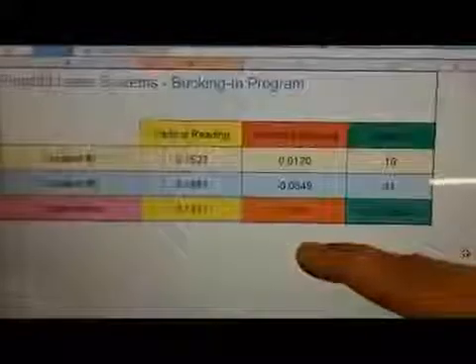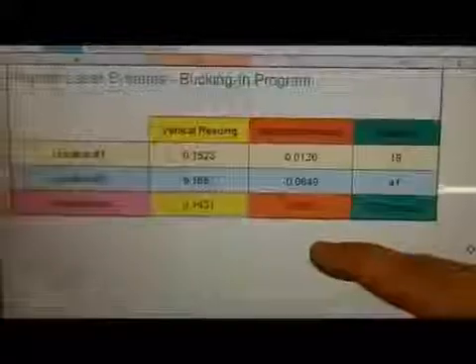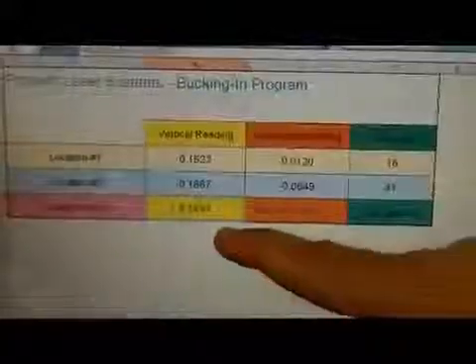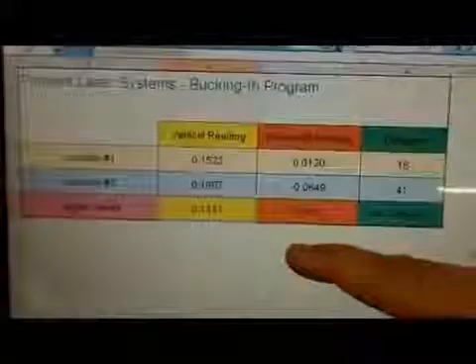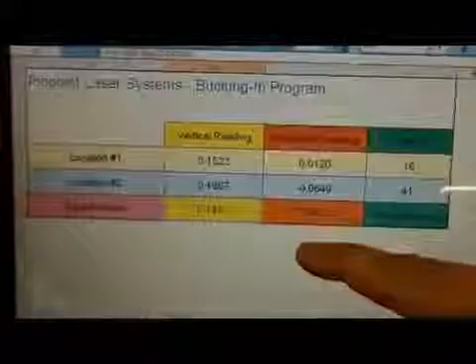Now I can adjust my four axis mount and my laser beam so that these numbers are displayed on the display unit from either one of the receiver locations.